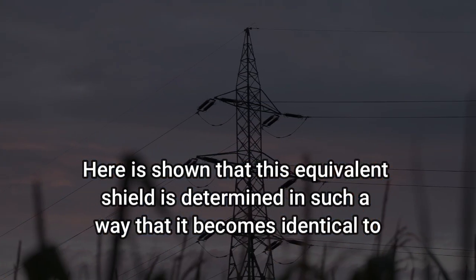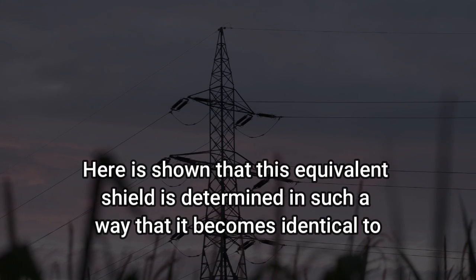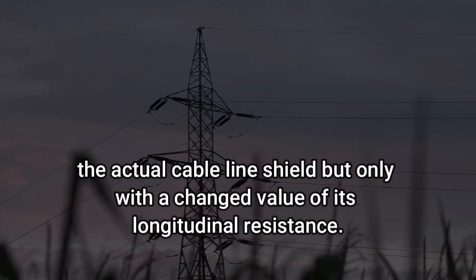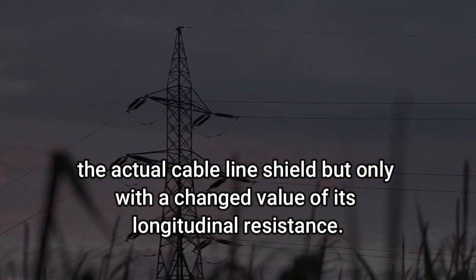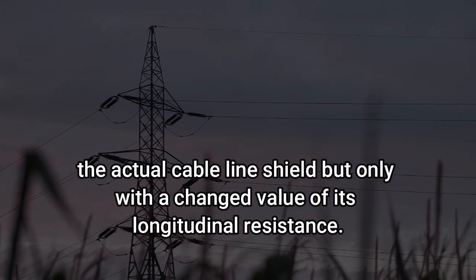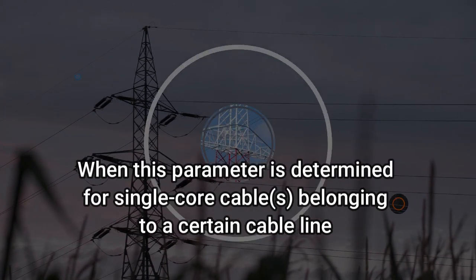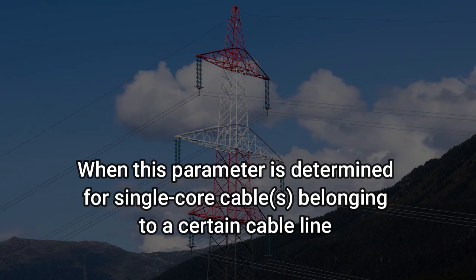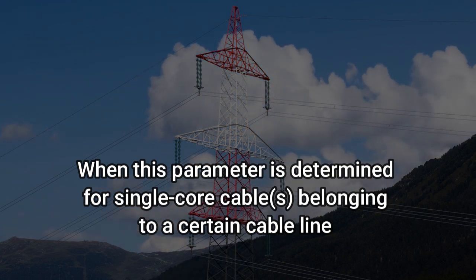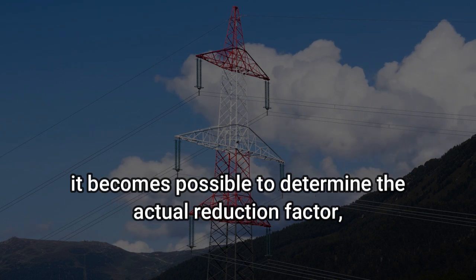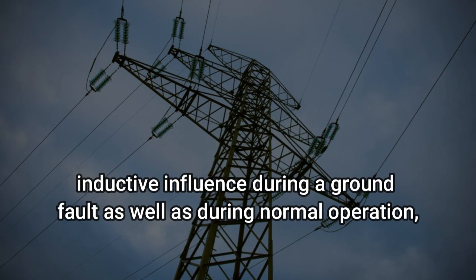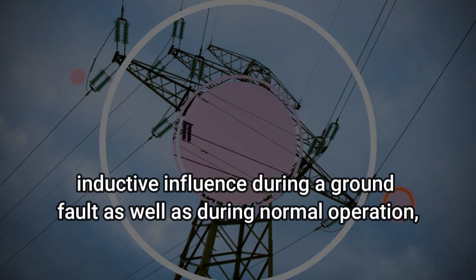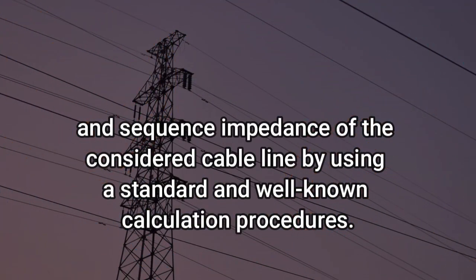Here it is shown that this equivalent shield is determined in such a way that it becomes identical to the actual cable line shield, but only with a changed value of its longitudinal resistance. When this parameter is determined for single-core cables belonging to a certain cable line, it becomes possible to determine the actual reduction factor, inductive influence during a ground fault as well as during normal operation, and sequence impedance of the considered cable line by using standard and well-known calculation procedures.